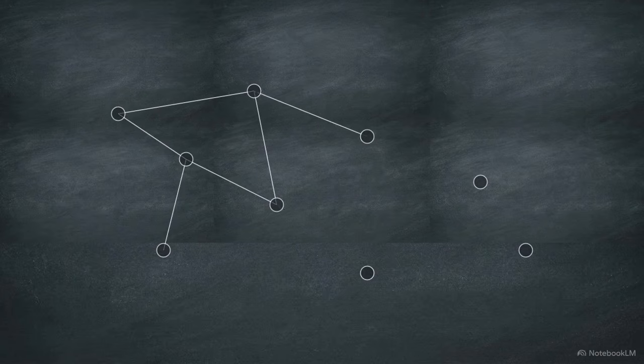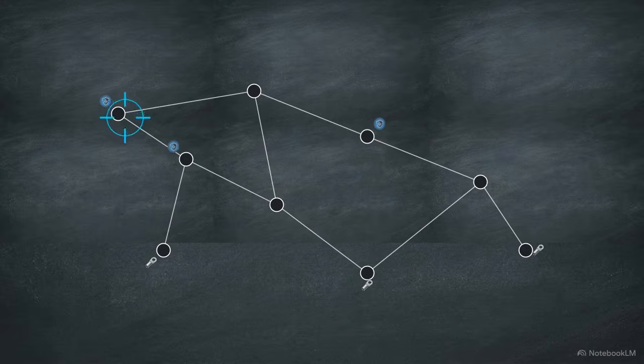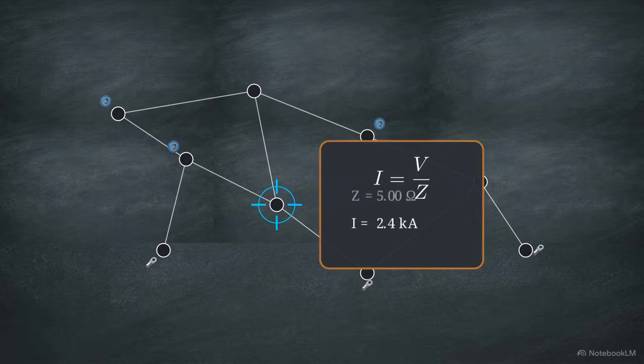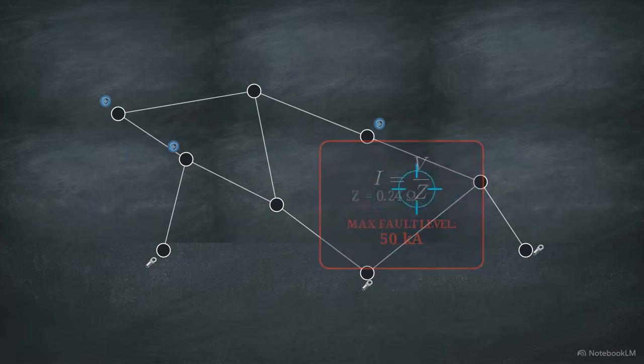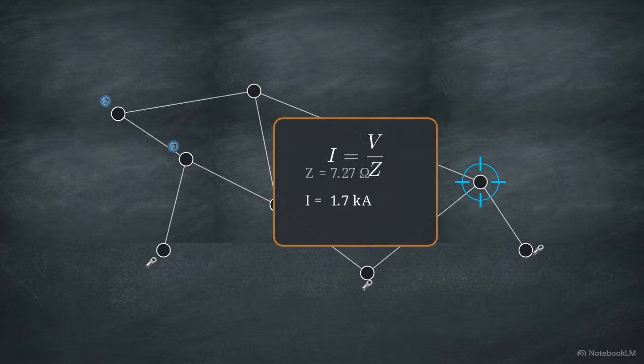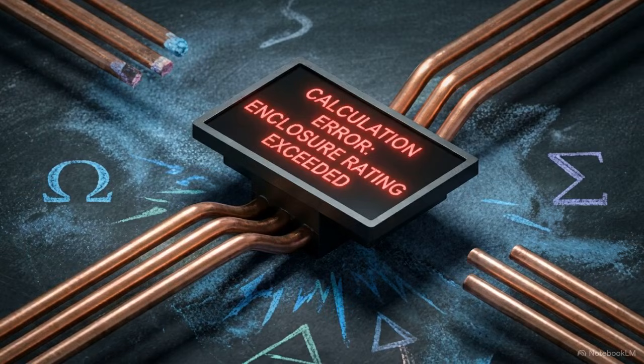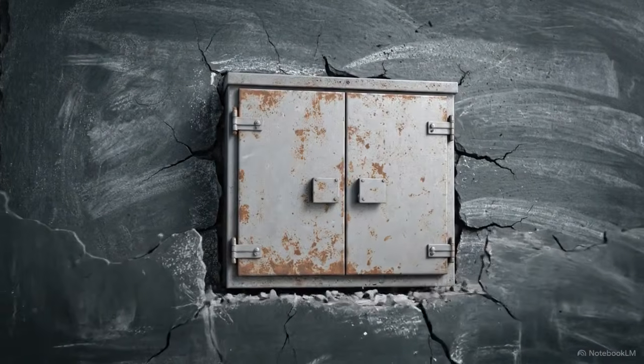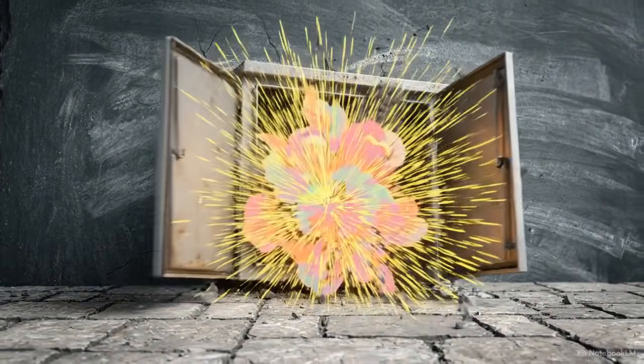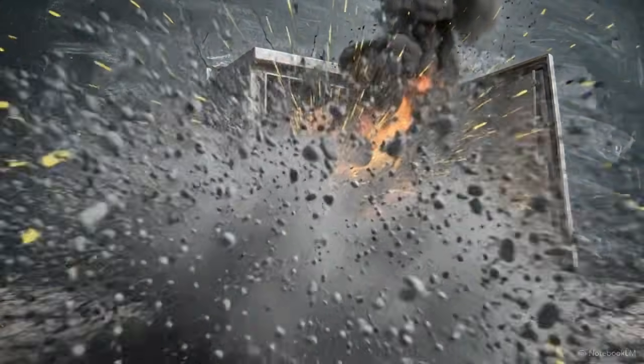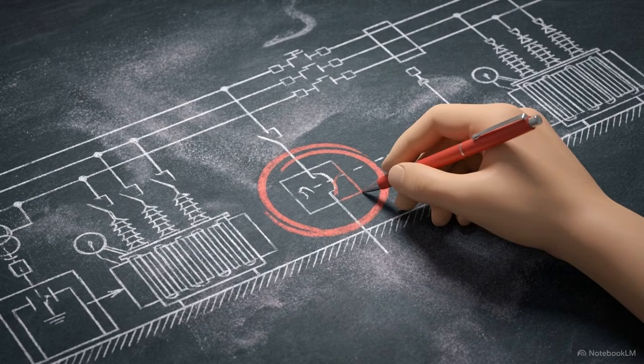To guarantee that strength, engineers calculate the fault level, measured in kiloamps. This requires analyzing the entire grid architecture to predict the absolute maximum explosive energy available at every single node in the power system. If those calculations are wrong, the consequences are disastrous. An underrated breaker attempting to stop a massive fault will fail to contain the arc, melt internally, and explode like a bomb. This is why short-circuit calculations are a mandatory part of electrical engineering.